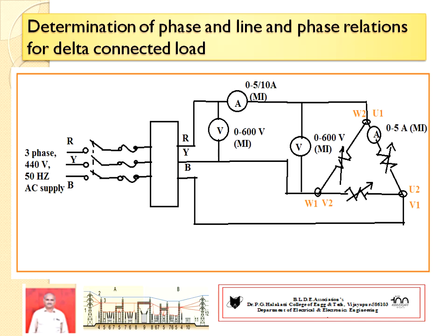You have to make common connections: the dissimilar ends of the windings are joined to form three common terminals. These three common terminals are used for further connection. Such a load connection is referred to as a three-phase delta connected load. Then one ammeter you connect in any one phase, U1 to U2, which reads the current referred to as the phase current.